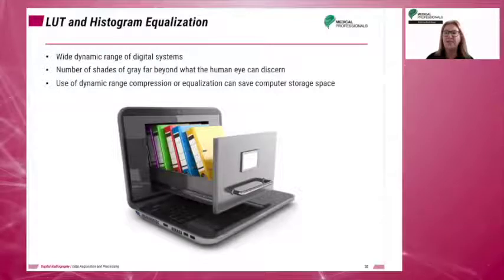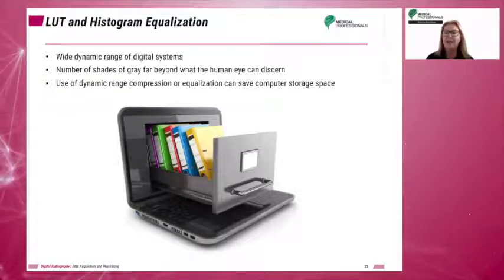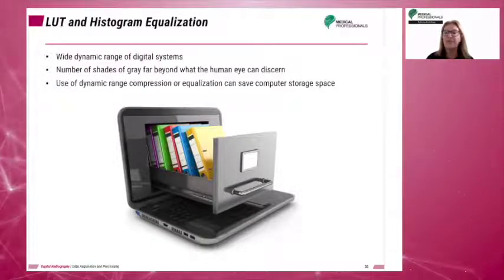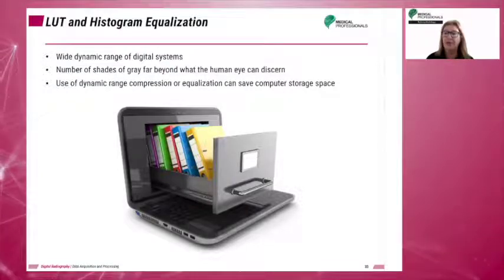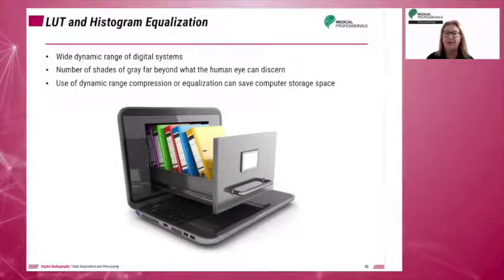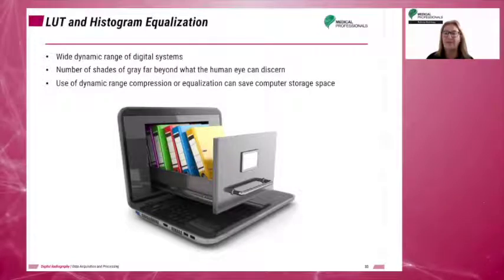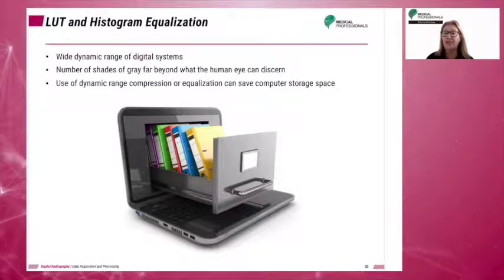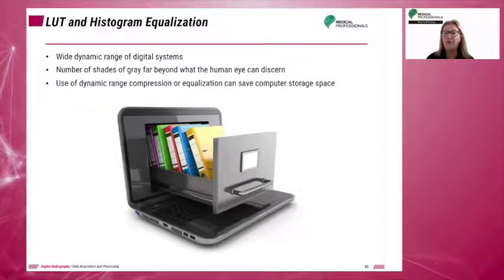Digital imaging systems are capable of representing a great number of gray shades based on the pixel bit depth, referred to as dynamic range. The range of gray shades that can be displayed by each pixel is far beyond what the human eye can differentiate. By compressing the dynamic range, computer storage space can be saved. The dynamic range can be compressed so that the lightest and darkest shades of gray are no longer visible on the displayed images.